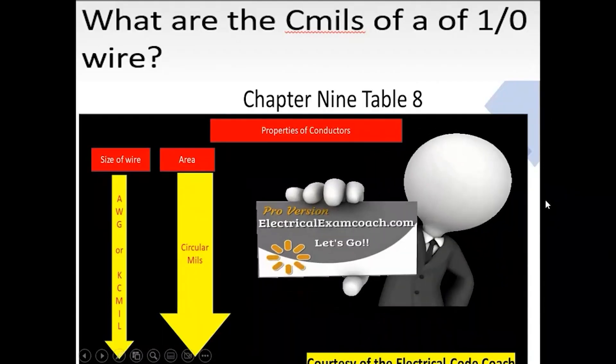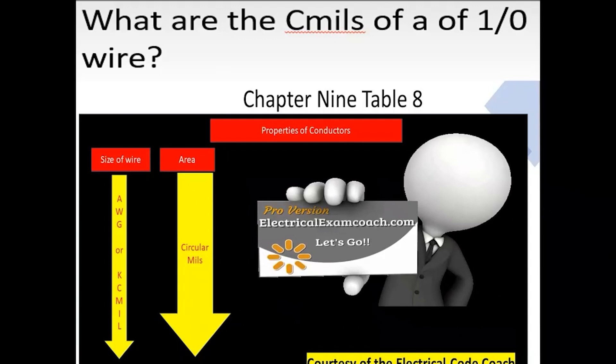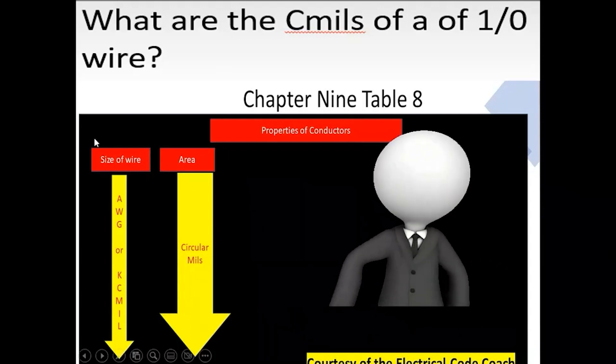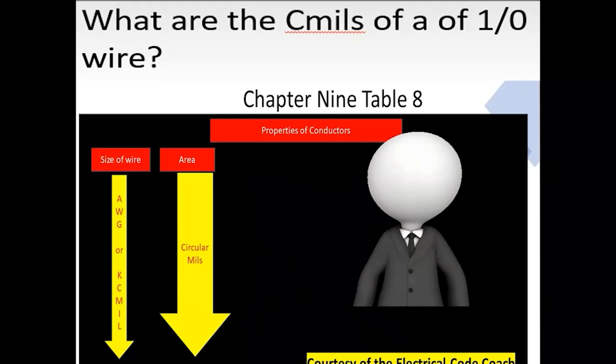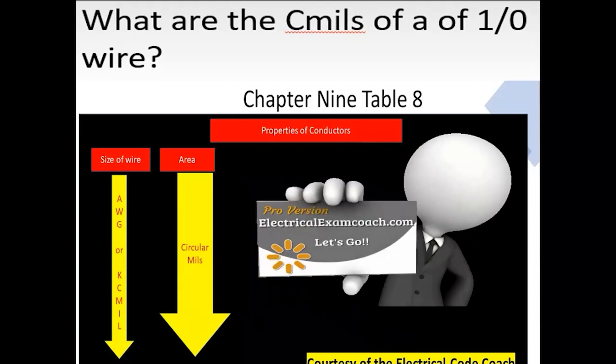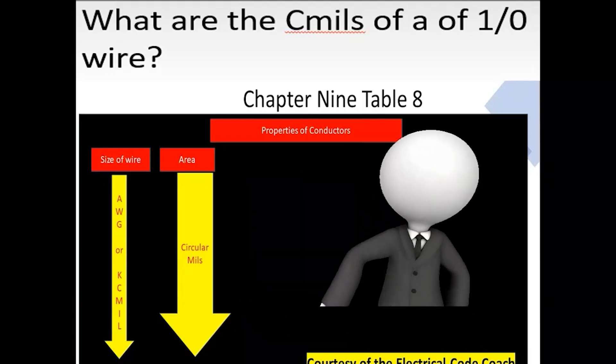And we're going to find the answer to this in Chapter 9, Table 8. When we get there, we're going to start on the left-hand side and find our size of wire. Then we're going to come over and we're going to cross over to our circular mils. And when we're going to use things like this is when we're doing voltage drop calculations, or if we're paralleling wires when we're doing grounding conductors.